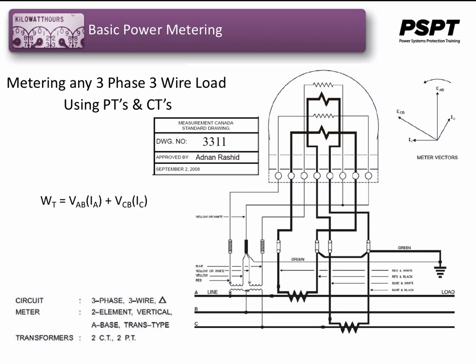And for a higher voltage, higher current circuit using PTs and CTs, such as Measurement Canada Standard 3311 shows here, the same equation holds true, where the first element takes in the voltage A to B with the red phase current, and the other element takes voltage C to B with the C phase current. And of course, you have to take into consideration the turns ratio of the CTs and PTs when you're coming out with your final answer.